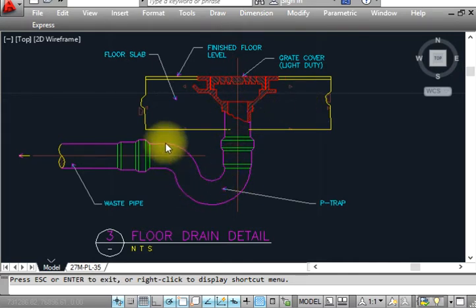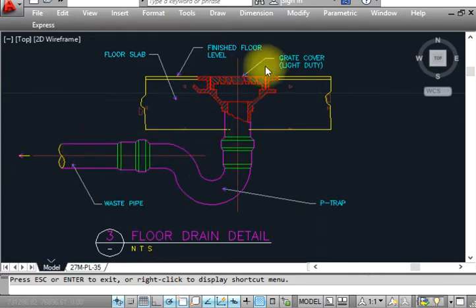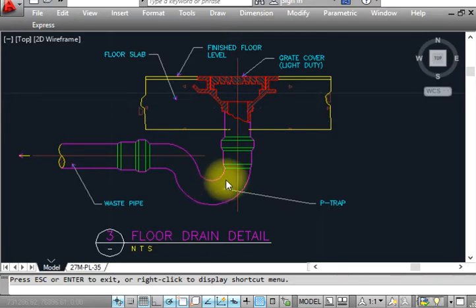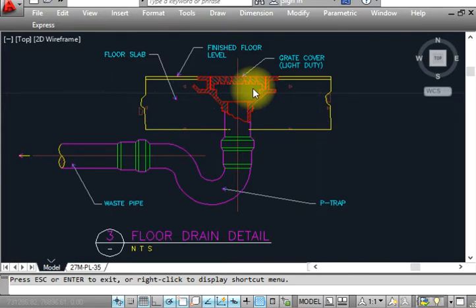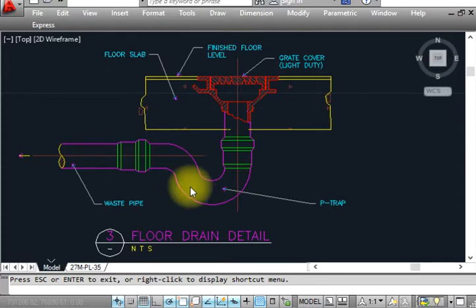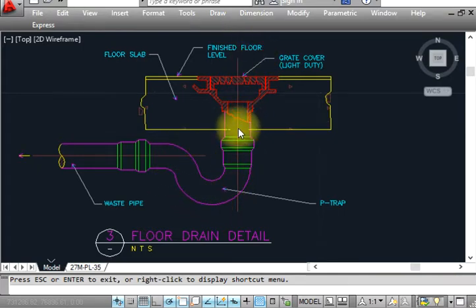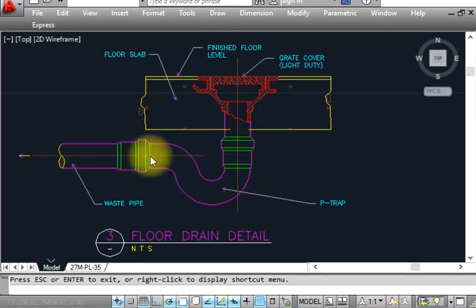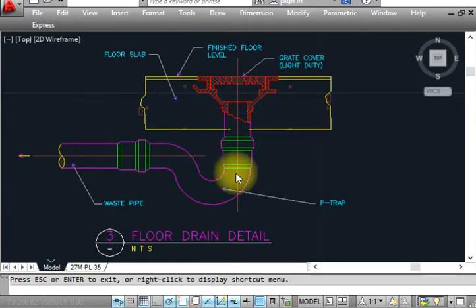This is a lab so this should have a P-trap. P-trap is compulsory because the water will be retained here in the P-trap, so the smell will not come outside. If you do not install the P-trap, the smell will spread across the whole floor. P-trap is compulsory to install in plumbing whenever you connect to the floor drain, sink, or WC. When you put water in, the water level will rise and some water will be retained, so whatever rotten things — garbage or food particles — the smell will not come outside because the water is retained.